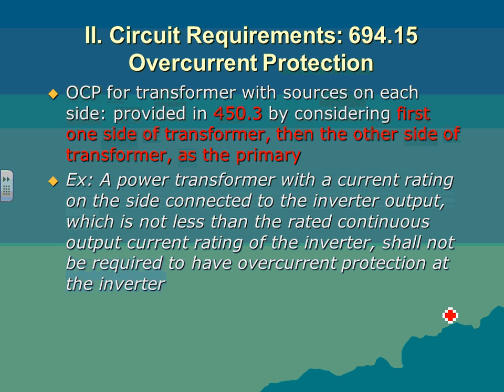Okay. So a transformer, if you guys are familiar, this is typical when you have a medium voltage system. You take the power and convert it to a higher voltage to drop it on the grid. If you do that, then you have a primary and a secondary. So you're bringing your output in here and dropping it to the grid at this point. Now, when you size your transformer, I know this is a little more detail, you have to consider this as the primary and size the overcurrent protection device based on it when you're pulling power this way. Then if the power is going that way, that will be your primary. So you take the two scenarios when you size your overcurrent protection device.